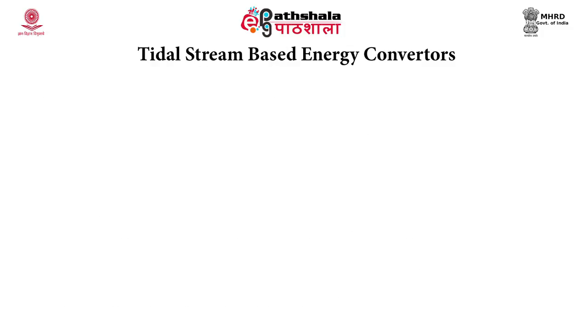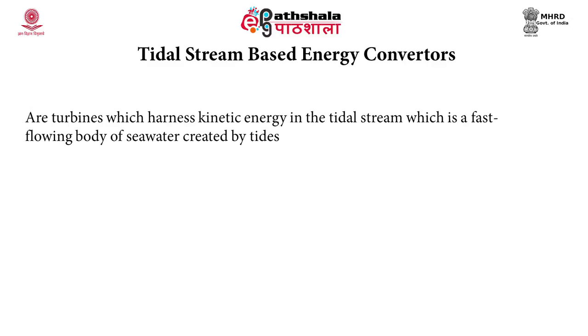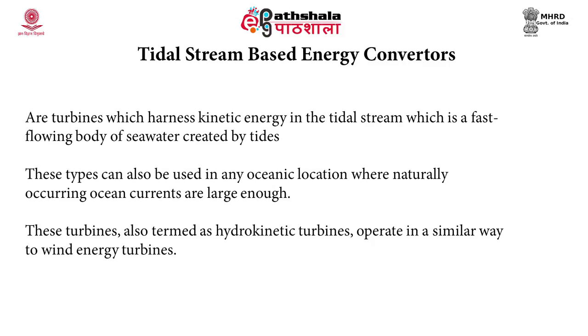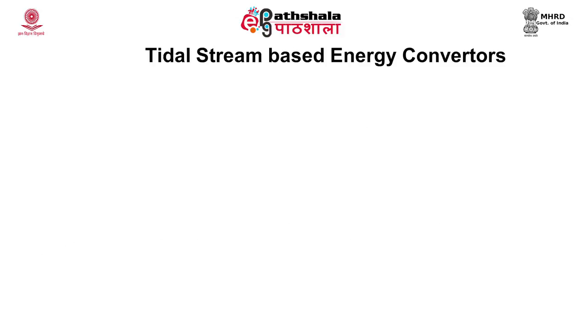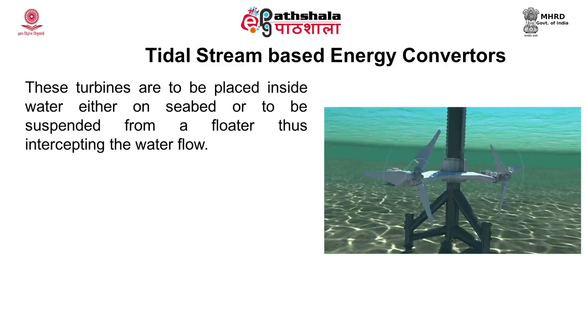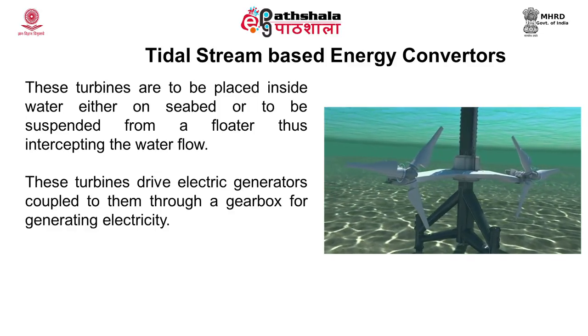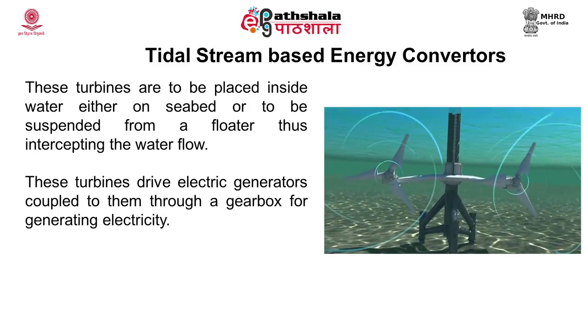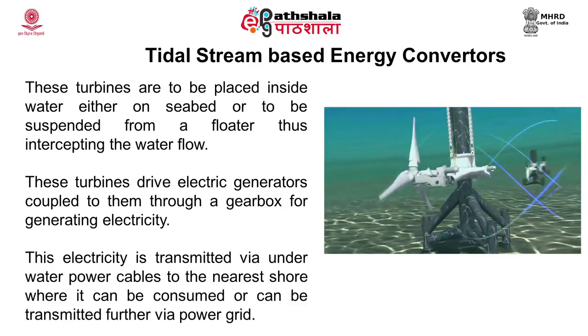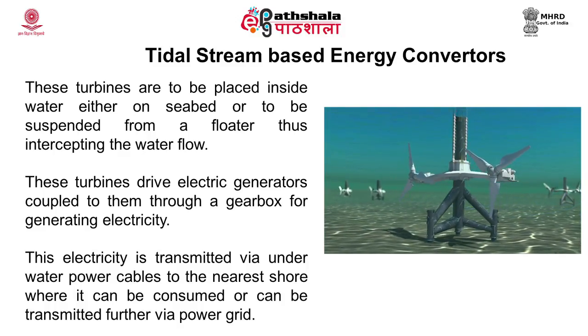Tidal stream-based energy converters are turbines that harness kinetic energy in the tidal stream, which is a fast-flowing body of sea water created by tides. These can also be used at any oceanic location where naturally occurring ocean currents are large enough. Also known as hydro kinetic turbines, they operate similarly to wind energy turbines and are placed inside water either on the seabed or suspended from a floater to intercept water flow. They drive electric generators through a gearbox, and the electricity is transmitted via underwater power cables to the nearest shore.